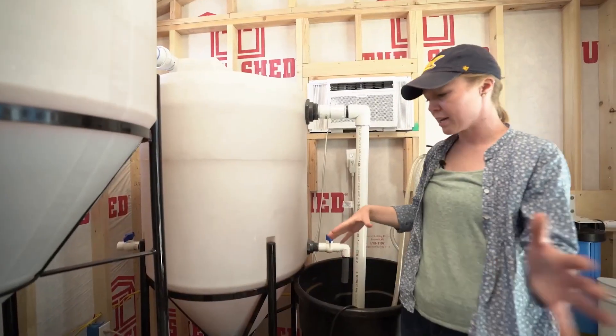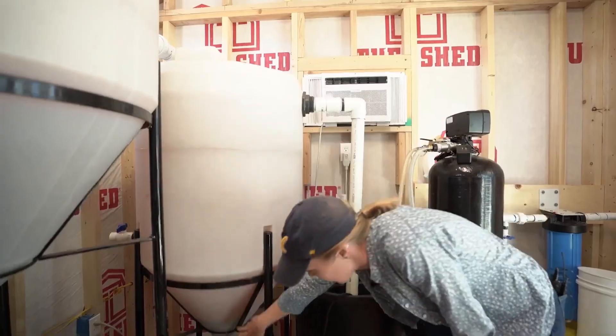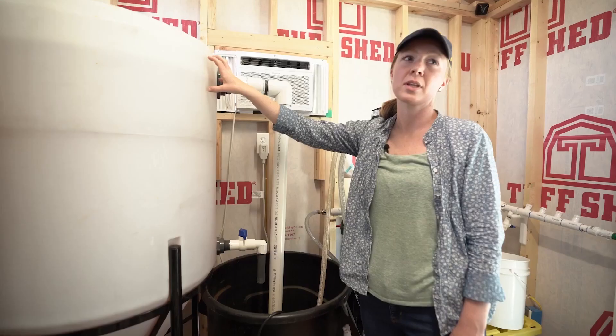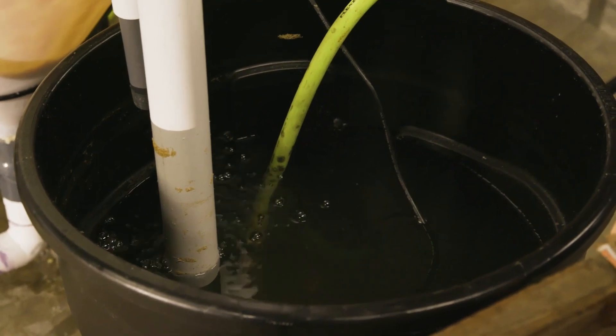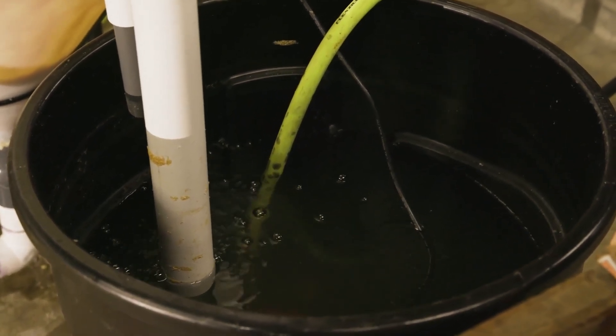We are then able to separate the arsenic just like any other suspended solids in water. So this is our settling tank, and kind of where all of the arsenic ends up is in the sludge, which you'll see being collected here at the bottom. The clear water on top of the settling tank overflows into a holding tank, so that we're able to pump all of that mostly clean water through the rapid sand filter.